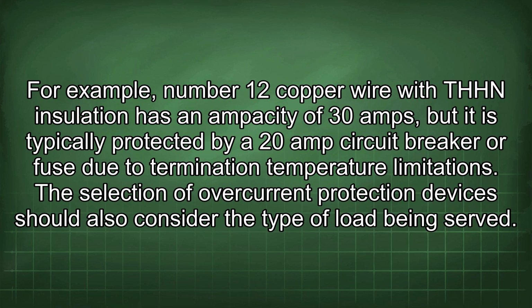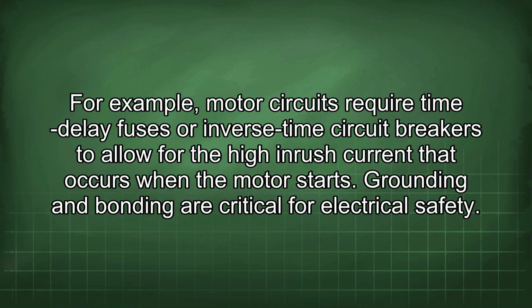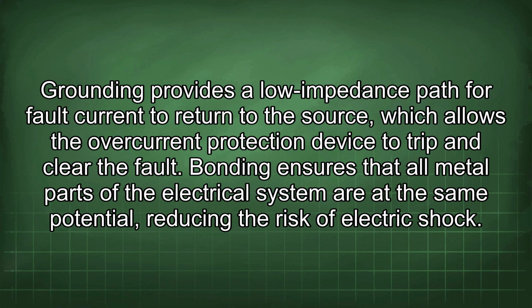The selection of overcurrent protection devices should also consider the type of load being served. For example, motor circuits require time delay fuses or inverse time circuit breakers to allow for the high inrush current that occurs when the motor starts. Grounding and bonding are critical for electrical safety. Grounding provides a low impedance path for fault current to return to the source, which allows the overcurrent protection device to trip and clear the faults.